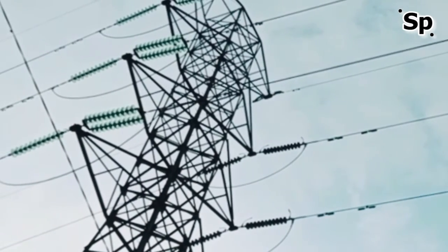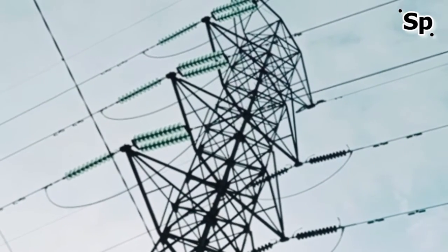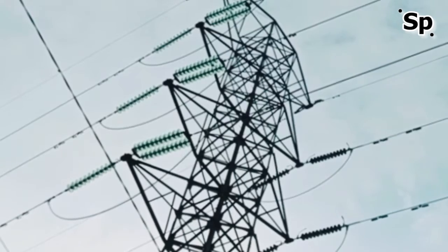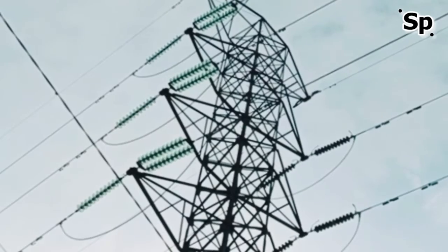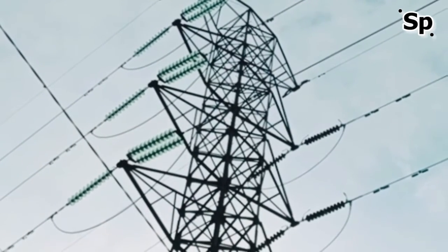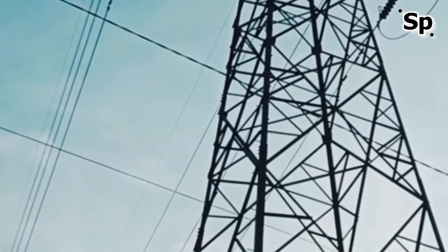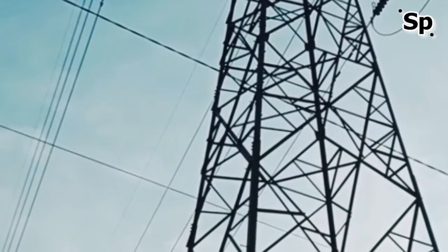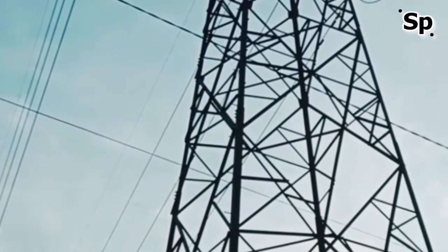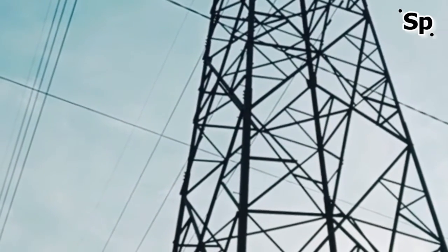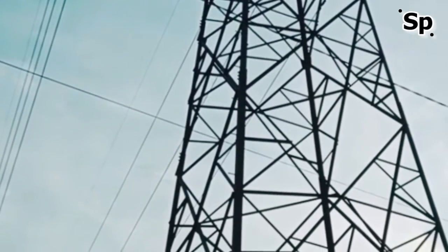Since overhead transmission wires depend on air for insulation, the design of these lines requires minimum clearances to be observed to maintain safety. Adverse weather conditions, such as high winds and low temperatures, can lead to power outages. Wind speeds as low as 23 knots, 43 km per hour, can permit conductors to encroach operating clearances, resulting in a flashover and loss of supply. Oscillatory motion of the physical line can be termed conductor gallop or flutter depending on the frequency and amplitude of oscillation.